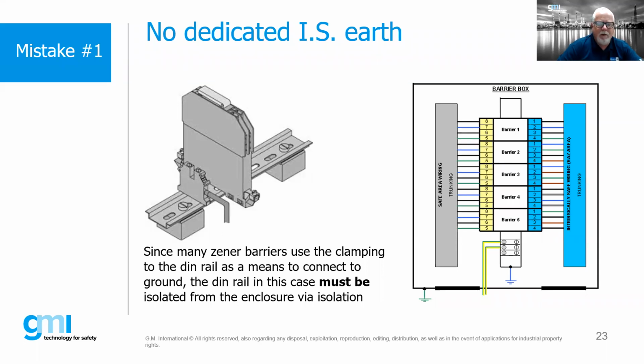Another question just came in: distinguish between power and signal earth. Generally, I'm considering normal earthing requirements. That's where we have all of our potential noise. It could be noise from our VFDs, harmonics, or just the general EMC noise you would find in a normal processing facility. That's all tied into your normal earth, which is designed to dissipate any potential fault condition. The reason we want the clean earth clean is that we don't want induced noise, currents, and all different kinds of interference coming into that earth, because we don't want an earth stray current coming up through the earth into our intrinsically safe system. And I think we show a slide about this in just a little bit.